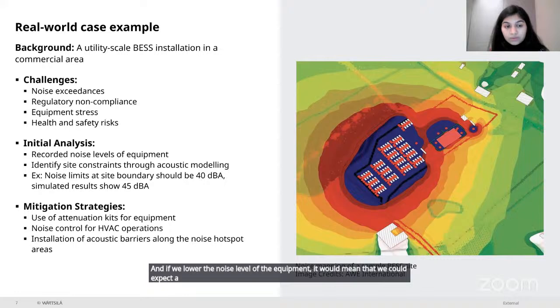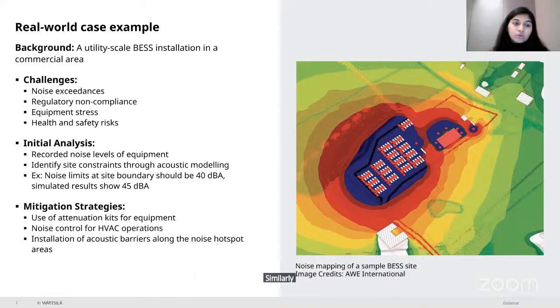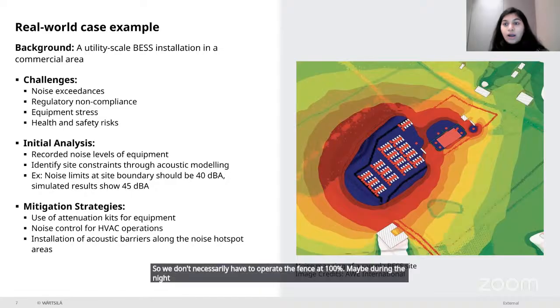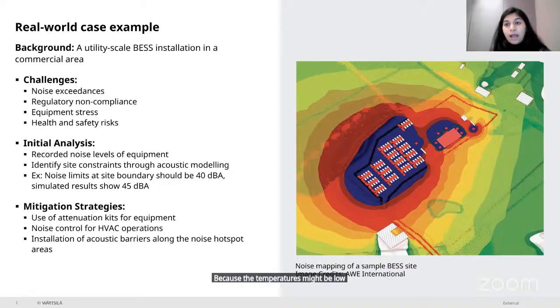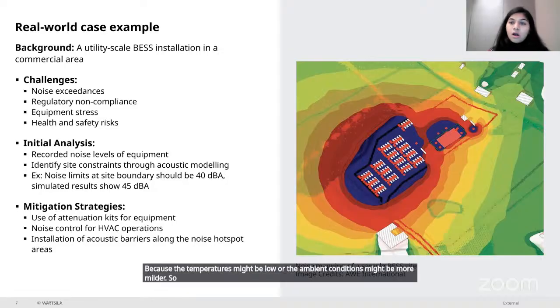If we lower the noise level of the equipment, we'd expect lower noise at the site boundary. Similarly, another mitigation strategy is noise control through operations — we don't necessarily have to run the fans at 100%. During nighttime, for instance, high fan operation may not be needed since temperatures and ambient conditions are milder. So we can use operational control and fan speed control to lower the noise.